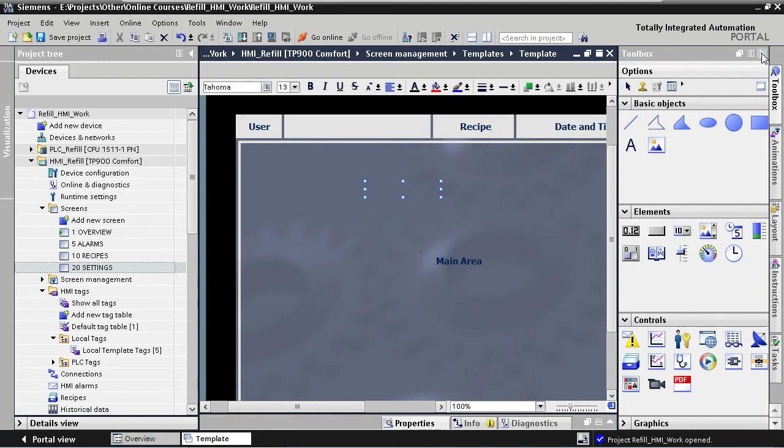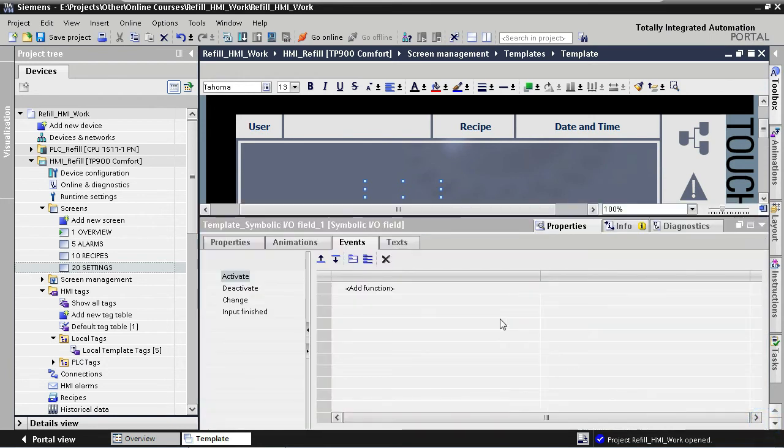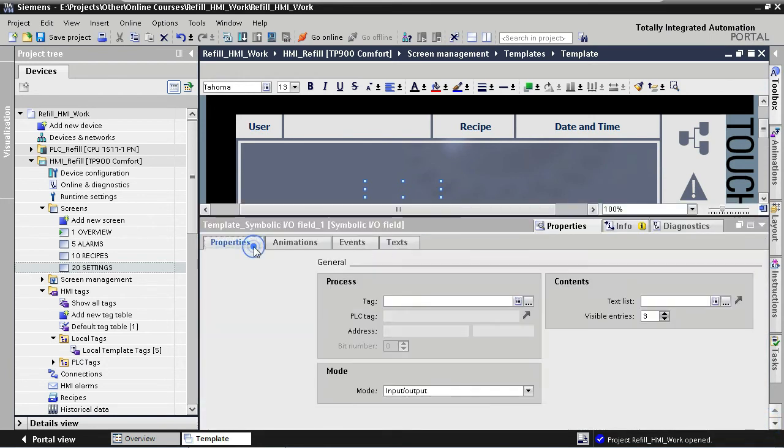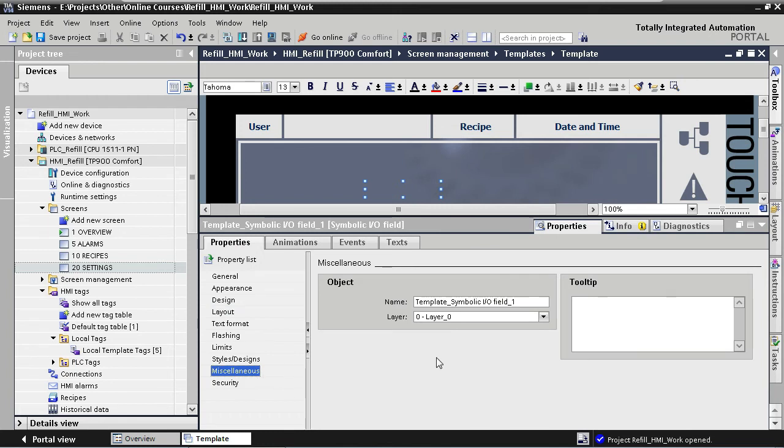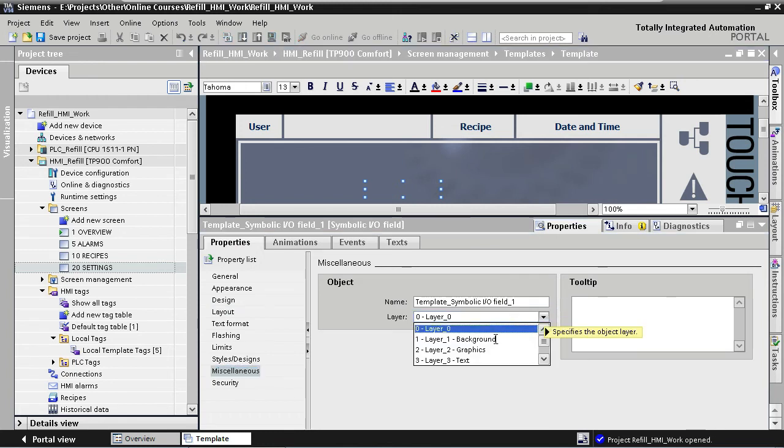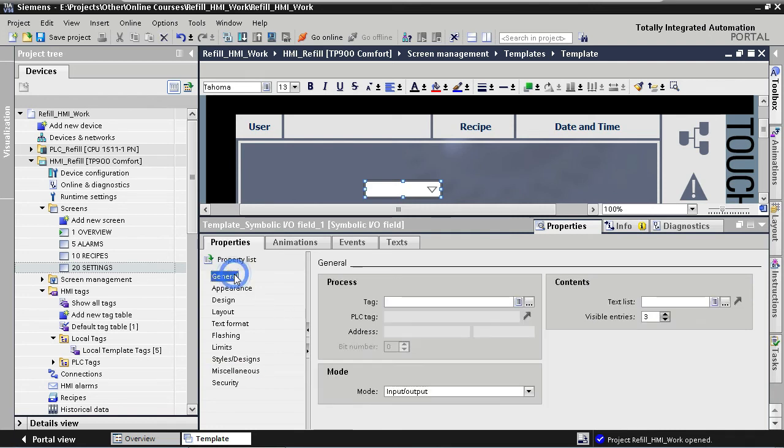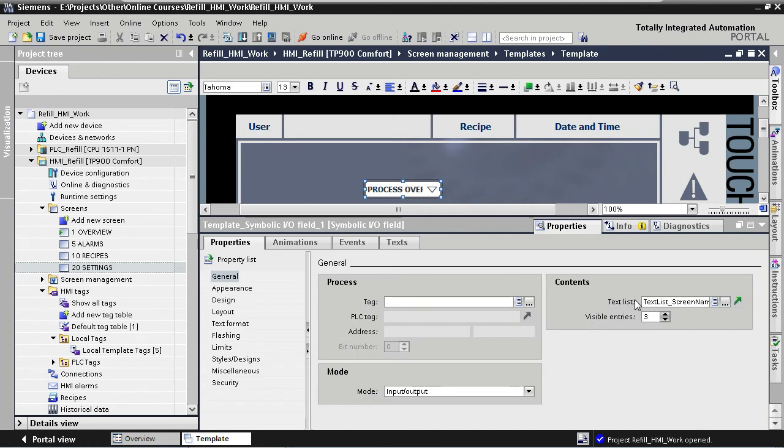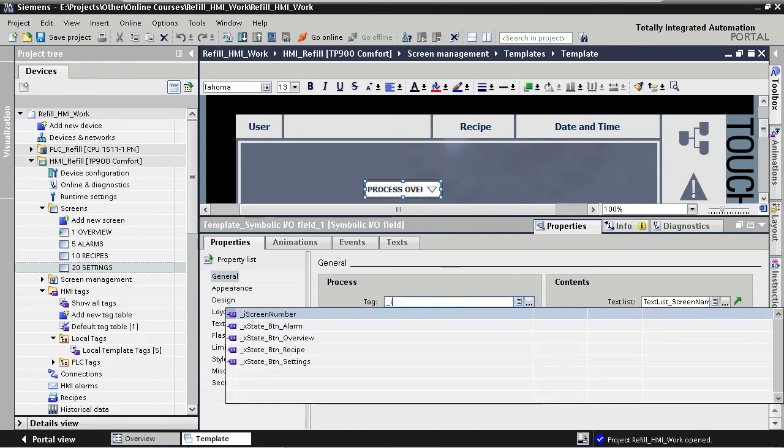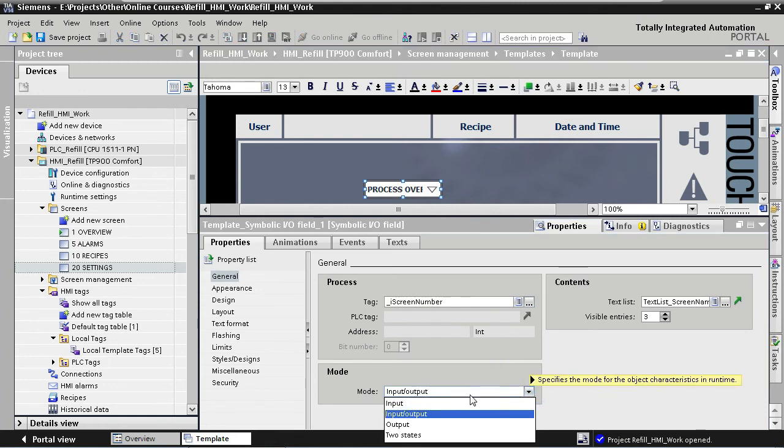Because it's a text, and it will be on top of our rectangle graphic, we start by assigning layer 3 to our element. Under General Properties, we are going to assign the text list that we've created in step 1, and the tag that we've created in step 2, to the element. So we select text list screen names for our text list, and screen number for our tag. We are only going to output the screen names. There is no need for any input functionality, so we change the mode down here to output.